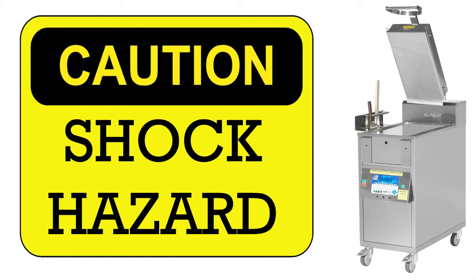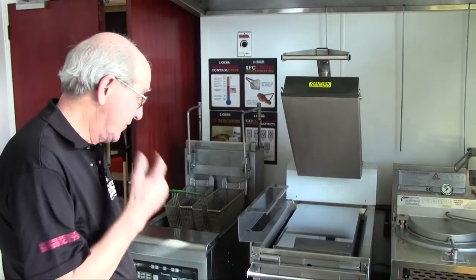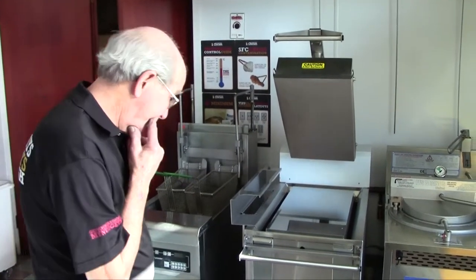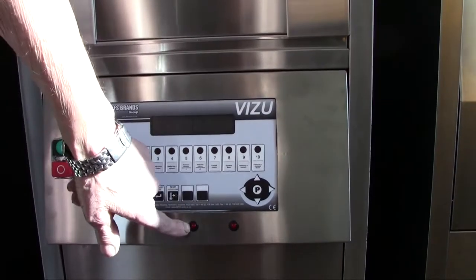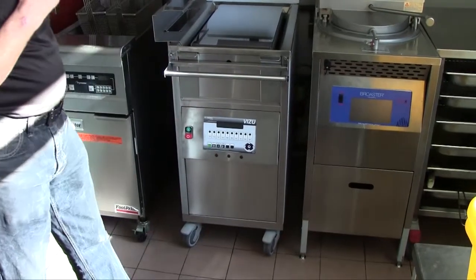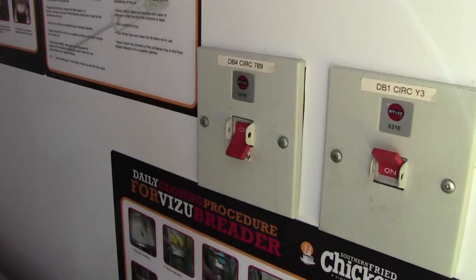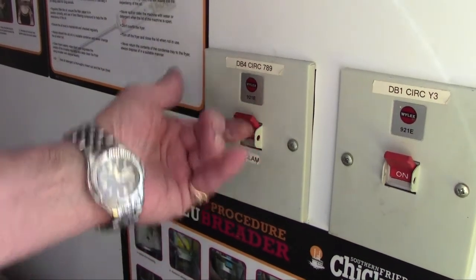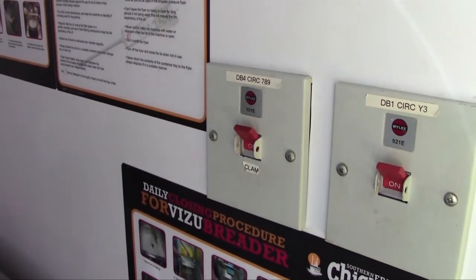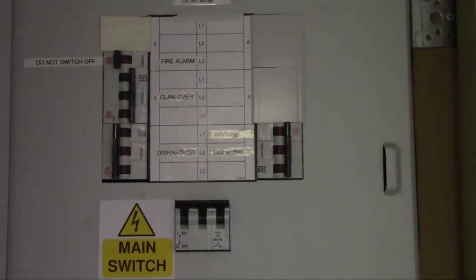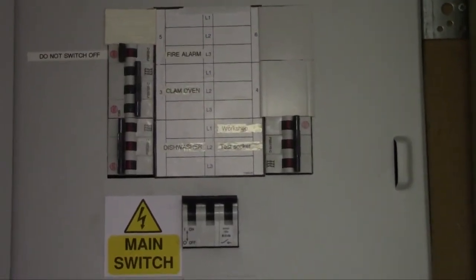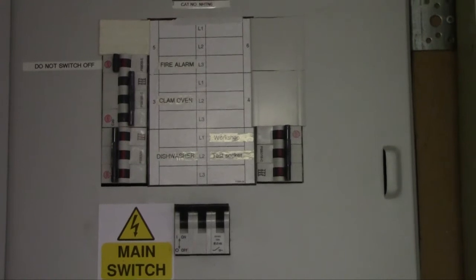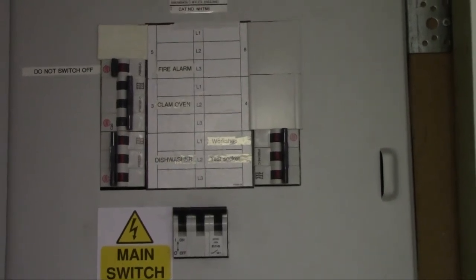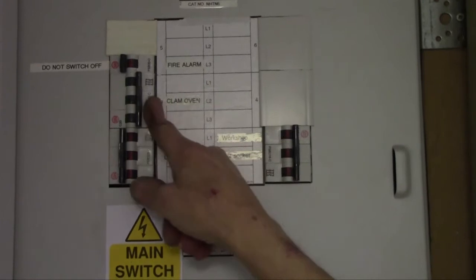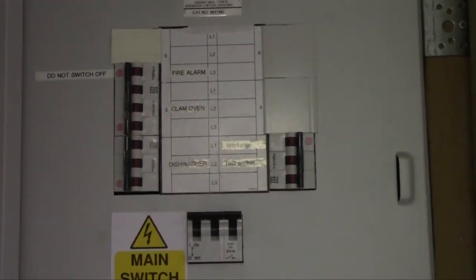Risk of electric shock. If the machine fails to start, first of all look and see that you've got the 3 indicator lights illuminated. Check also that if they're all out, that the isolation switch on the wall is on. We've turned it on and the machine still hasn't started. You must now check exterior to the machine, which would be the main distribution board. Check at the main distribution board that the supply hasn't tripped. In this case it has.